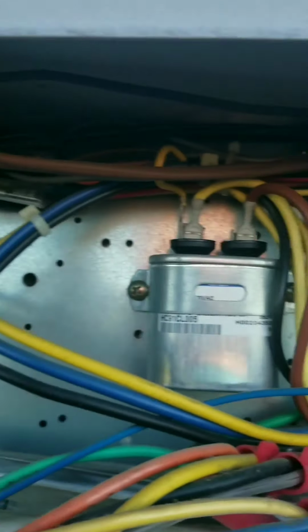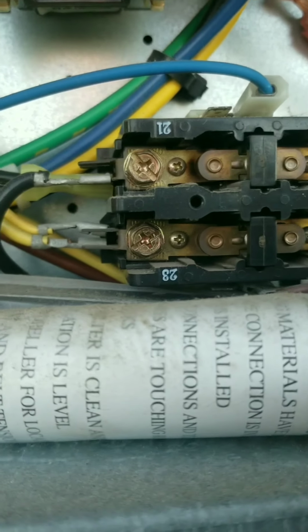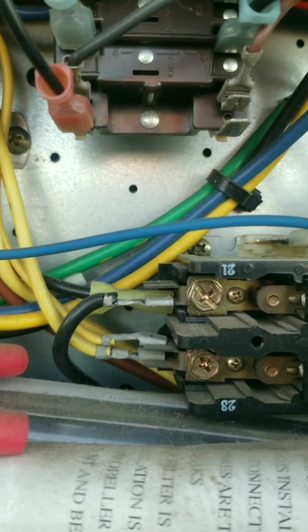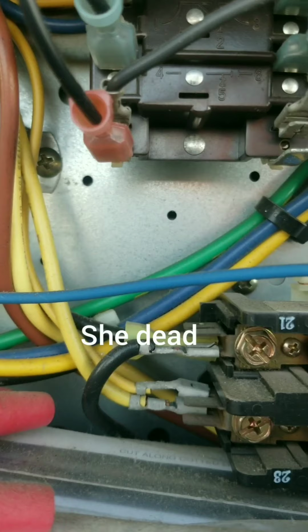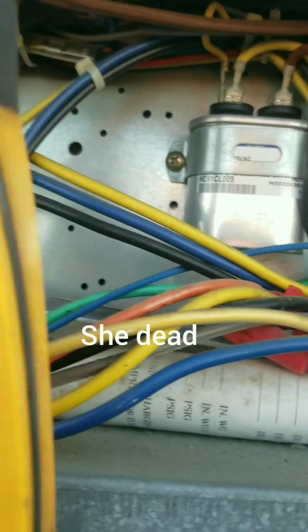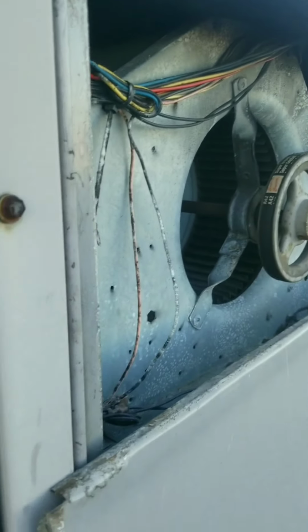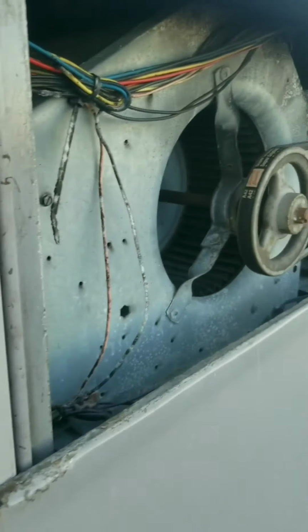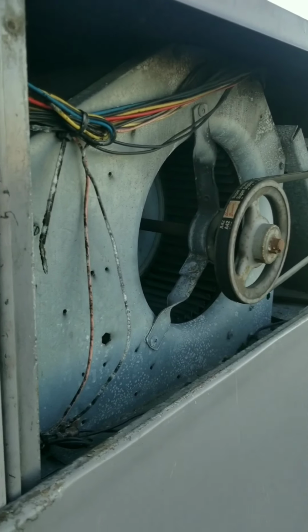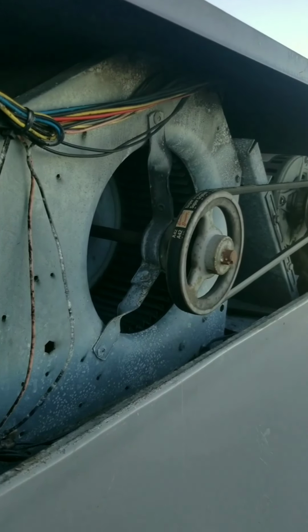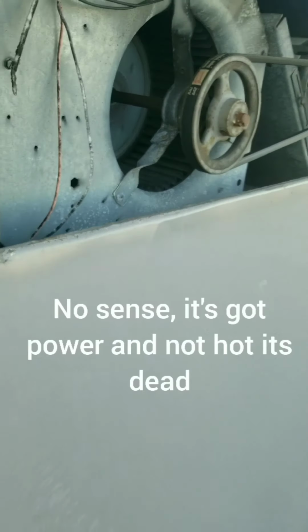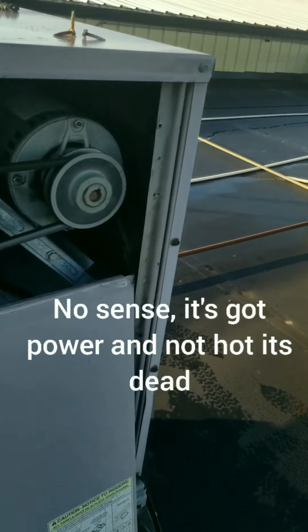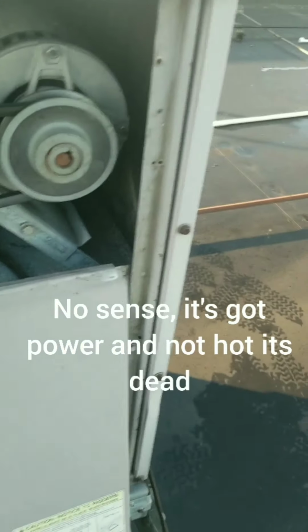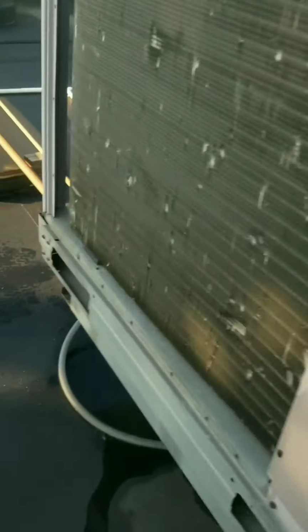And we've got 480 volts. The other side of our blower motor is powered from the main power all the time. And we got 480 volts. So we got a bad blower motor. We'll ohm it out to be sure, but I've got 3 legs of power. Blower motor's got power. She dead. And it's not warm, so it's not even trying to run now. You heard the bearings. Let's go cut the power off.